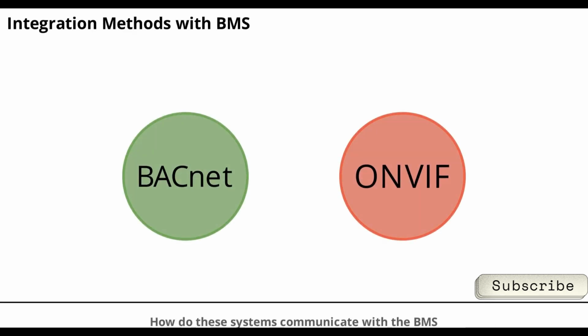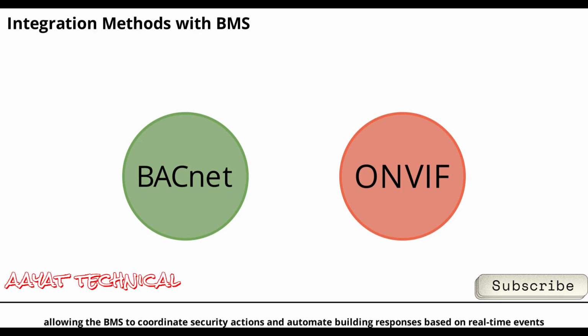How do these systems communicate with the BMS? Integration is achieved using industry-standard protocols and APIs. Access control systems often use BACnet IP, Modbus, OPC, or REST APIs to share door status, user events, and commands with the BMS. CCTV systems typically integrate via ONVIF, RTSP streams, HTTP APIs, or SNMP, enabling live video feeds and event-triggered snapshots. These methods ensure seamless data exchange, allowing the BMS to coordinate security actions and automate building responses based on real-time events.